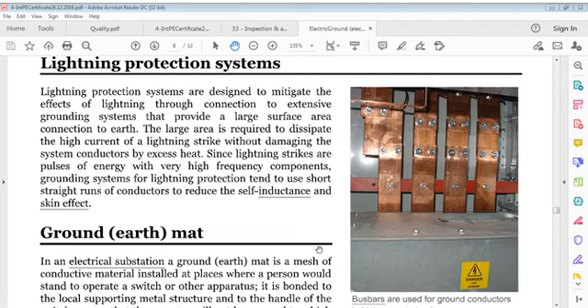I repeat, lightning protection system. Lightning protection systems are designed to mitigate the effects of lightning through connection to an extensive grounding system that provides a large surface area connection to earth. Large areas are required to dissipate the high current of a lightning strike without damaging system conductors by excess heat. Since lightning strikes are pulses of energy with very high frequency components, grounding systems for lightning protection tend to use short straight runs of conductors to reduce self-inductance and skin effect. Very complicated paragraph.